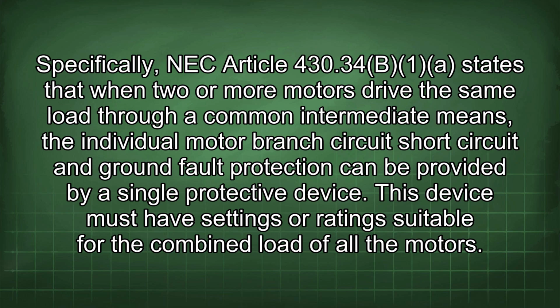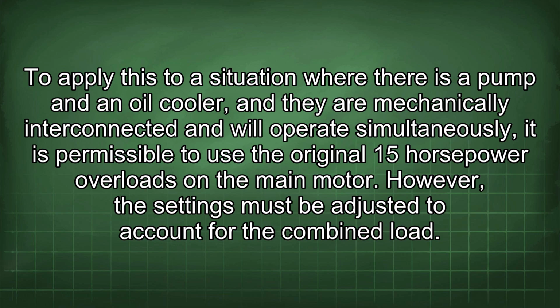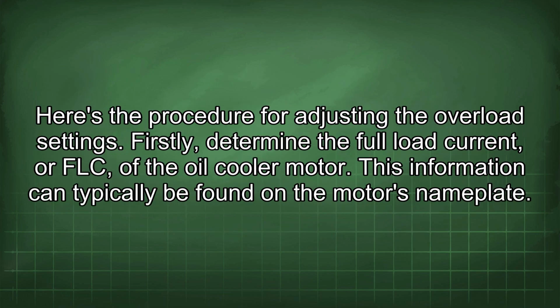This device must have settings or ratings suitable for the combined load of all the motors. To apply this to a situation where there is a pump and an oil cooler, and they are mechanically interconnected and will operate simultaneously, it is permissible to use the original 15 horsepower overloads on the main motor. However, the settings must be adjusted to account for the combined load. Here is the procedure for adjusting the overload settings.